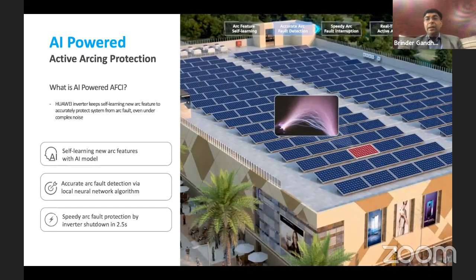So Huawei has brought in artificial intelligence powered arcing protection. Here in the video you can see what the causes of arcing are, and how AI powered AFCI is developed. We are collecting all the arc fault data from the site, and there's an inbuilt chip in the inverter which stores all the data and then analyzes the arc fault against the conditions, and within 2.5 seconds it can accurately detect the fault. So here you can see the fault being detected by the inverter.